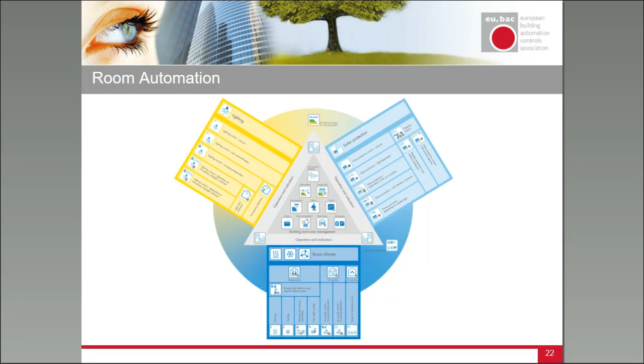Now here on this slide I'm going to visualize a little bit more in detail how this is technically set up. On the right hand side, we actually see equipment installed in a room. And you remember from my chart before, in the room we have to detect whether there is a demand for energy in the room, whether the room is used or not. So in such a room control we are using presence detectors and illumination sensors to control the light. With such a presence detector I also know if people are present. In some cases I can even count the number of people in the room. There are CO2 sensors installed in a room. With these CO2 sensors I'm measuring the quality of the air, but that's also an indirect indication of the number of people who are present in the room.